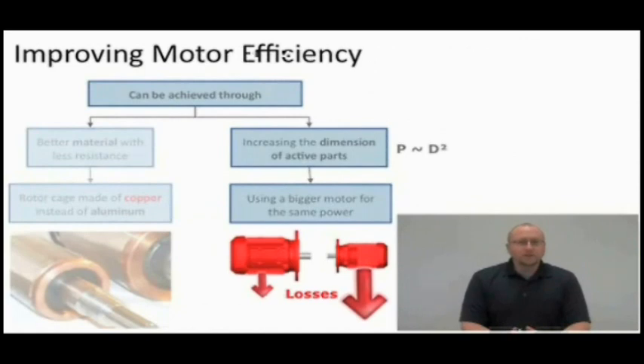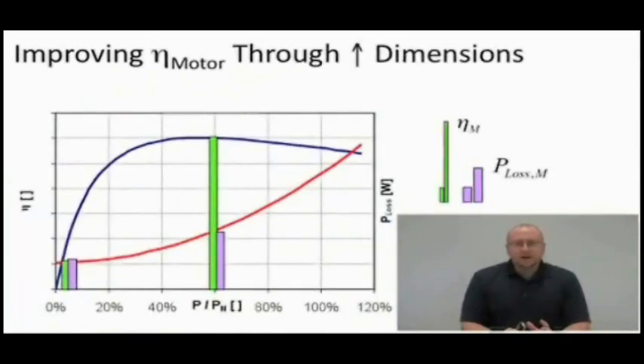Now the second way that we can make an asynchronous motor more efficient is by over-dimensioning. Now this may sound kind of weird, but let's think about it this way. Looking at this efficiency versus load curve, let's think about a car engine or a car motor instead of an asynchronous motor. Your car is designed to operate at a certain speed, and most of the mile per gallon ratings in the US are here. They're based off of 55 miles per hour. If you go faster than 55 miles per hour, you're going to use more gas. And if you go slower than 55 miles per hour, you're going to use more gas. You use more gas in the city than on the highway, and that's also due to starting and stopping. But you know, the big picture is that the efficiency of your motor changes at different speeds or different loads.